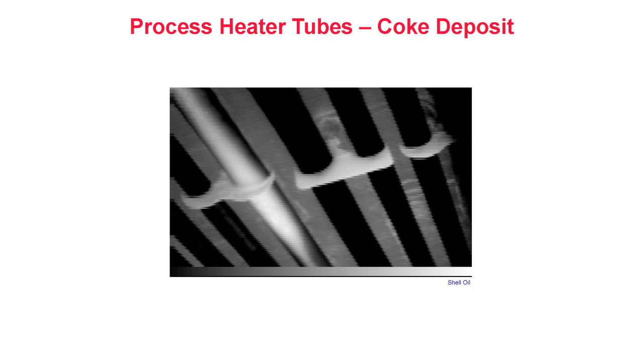Process heater tubes. Coke deposit. This thermogram shows a hot tube within a process heater used to refine crude oil. The white area indicates the presence of a coke deposit within one of the tubes. Left undetected, coke deposits can lead to irreversible tube damage and catastrophic failure. Thermography permits inspections to be conducted for heaters where visual inspections are not possible due to visually opaque flames.